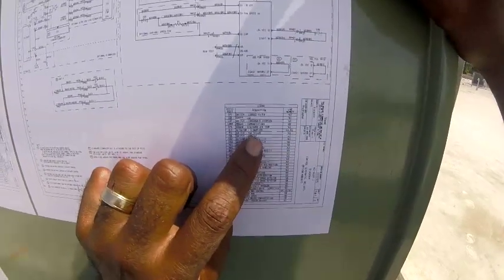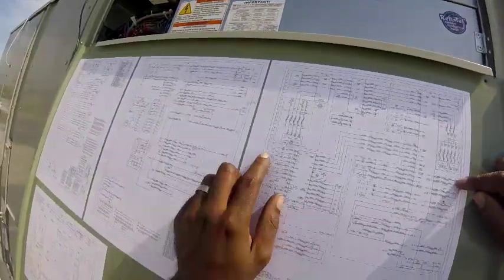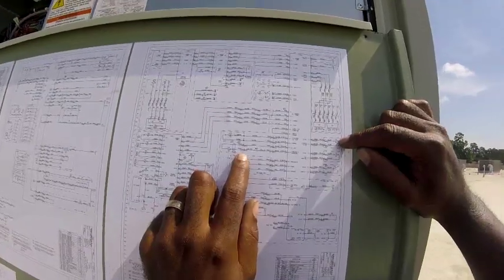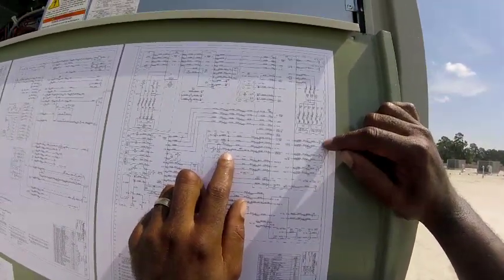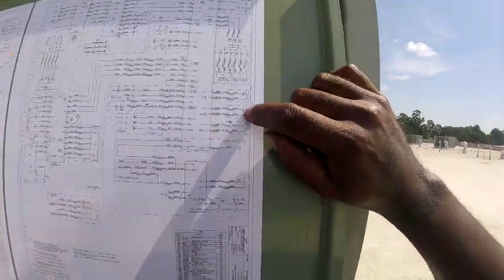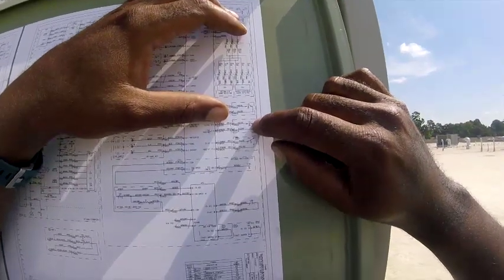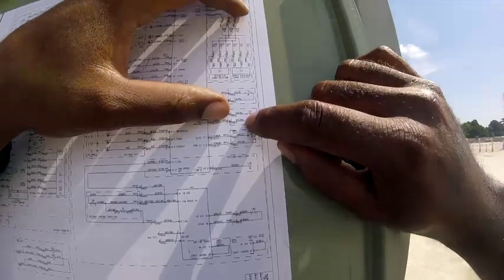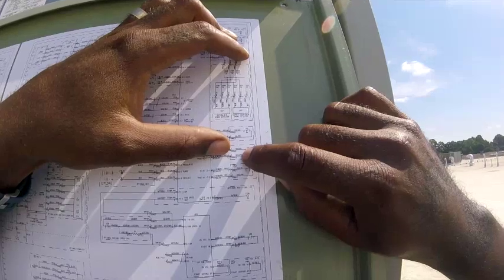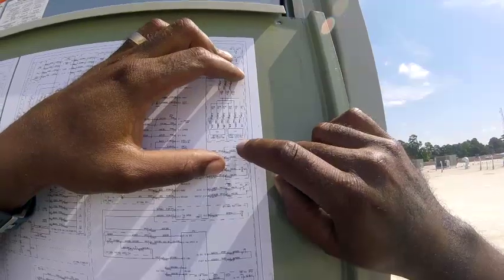I know it's not the frost stat. I think it's a fan failure. I look at 145. I think that's the switch right there. It was normally closed. And they come in, the red wire, yeah, and that purple wire right there. So it's 102 and 101C. It's two of them in there.